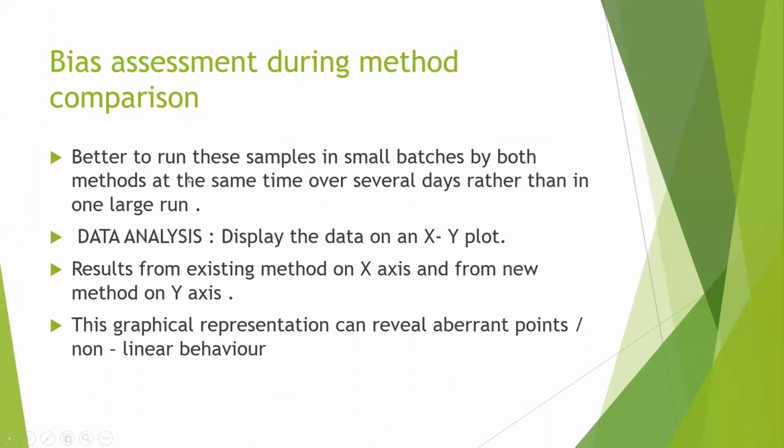Now, it is better to run these samples in small batches by both the methods at the same time over several days rather than 20 in one run. The reason for that is pretty obvious, because when you run the samples in small batches over several days, you are providing more challenge in terms of variation: temperature variation, operator variation, controls have been run, instrument maintenance has been done, ancillary reagents have been changed, water quality may have been a little different from day to day. Therefore, you are subjecting your experiment to more stresses and making it more robust. So it's better to run these in small batches rather than do all 20 in one large run. It is advisable to do them.